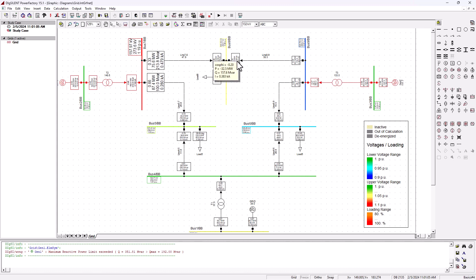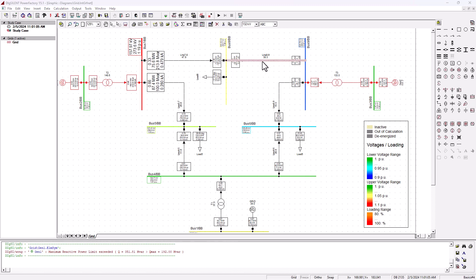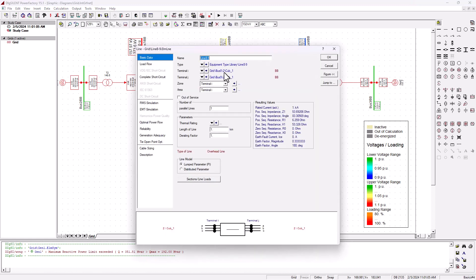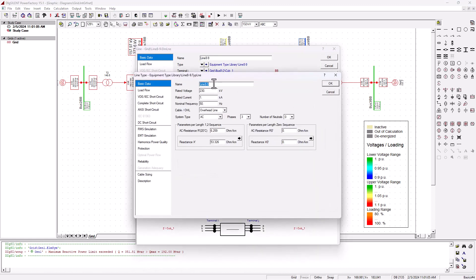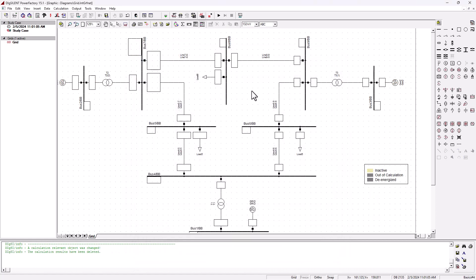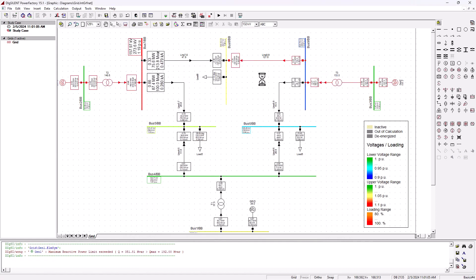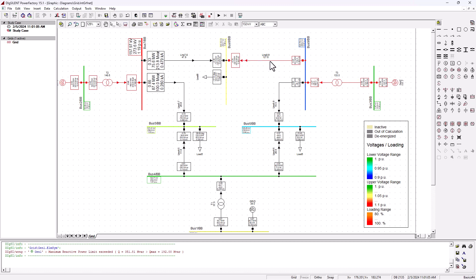If you close this and check line eight to nine, it says here that it's 38.3 percent overloaded. If we look at the current that's flowing from bus bar nine to bus bar eight, we've got the current of 0.383 kilo amps, so basically 383 amps is flowing. If we double click onto this line and we change the current rating here to 0.3, and we run the simulation or execute a load flow analysis again, you can see that the line is now 127.6 percent overloaded because we are way above the rating of this overhead line.